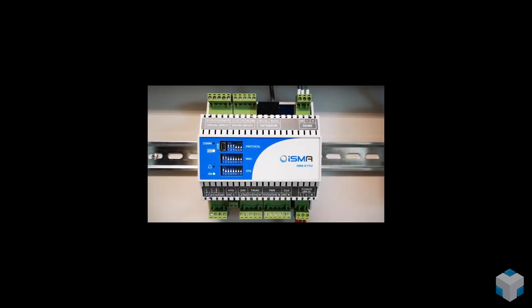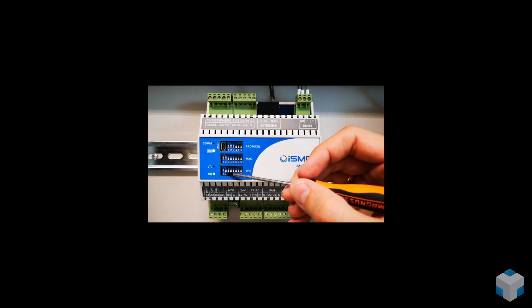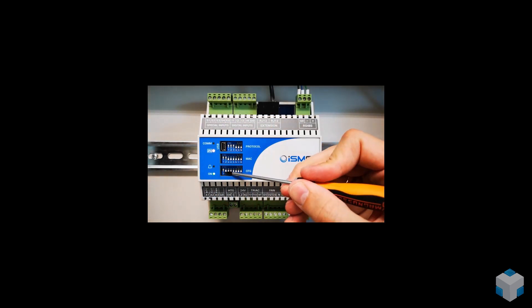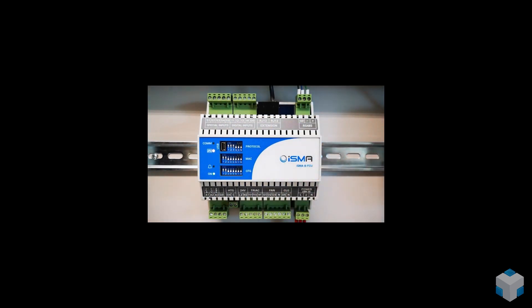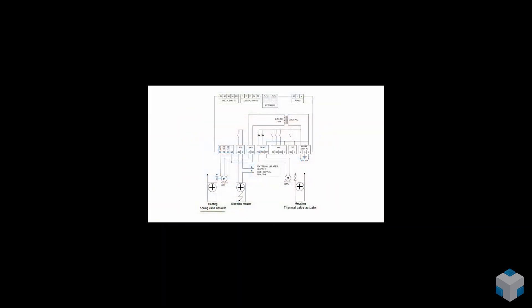The second configuring DIP switch selects if our fan coil unit controller will work with a single heating device, first stage only, or with two heating devices, basic first stage and additional second stage.